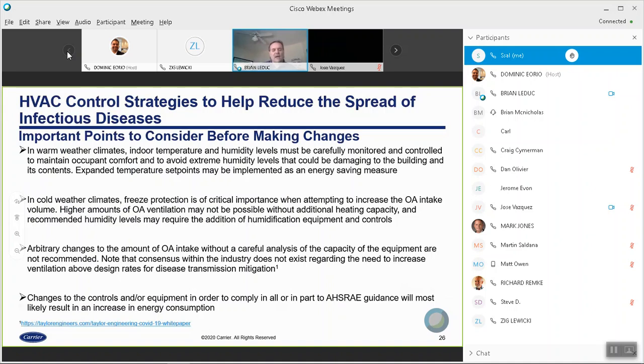We've recently done a lot of updates to our Logic library to improve how our freeze protection sequences work. So you want to make sure that you're running the latest and greatest applications. Higher amounts of outside air just might not be possible unless you have additional heating capacity. I'd imagine in Wisconsin or in Chicago, in the middle of the winter, you're not going to want to drive that outside air damper open beyond a certain point. The system's not going to be designed for it.